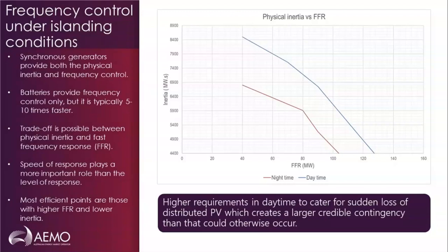A key finding of the analysis was that we always need a combination of synchronous generators and batteries. Synchronous generators, obviously, first and foremost, needed to provide system strength, and by virtue of being there, they would inherently provide the physical inertia, and they come with some frequency response as well, which is relatively slow. On the other hand, batteries don't provide any physical inertia or anything of that nature. What they do is provide a very fast speed of response for a frequency disturbance, which, as I mentioned previously, in our experience is 5 to maximum 10 times faster than what we can see from the turbine governor of a synchronous generator.